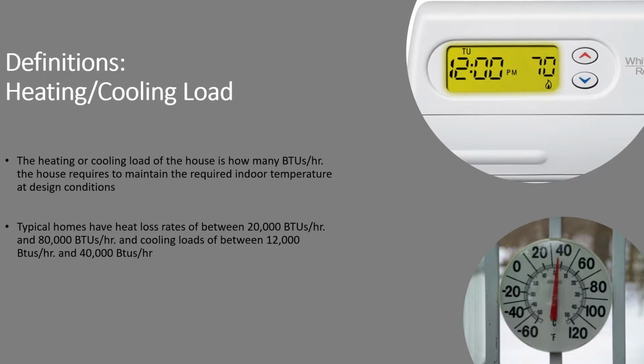Definitions: heating and cooling load. The heating or cooling load of the house is how many BTUs per hour, just like how the equipment is rated, the house requires to maintain the required indoor temperature at design conditions. Typical homes have heat loss rates of between 20,000 BTUs an hour and 80,000. Cooling loads typically range between 12 and 40,000.